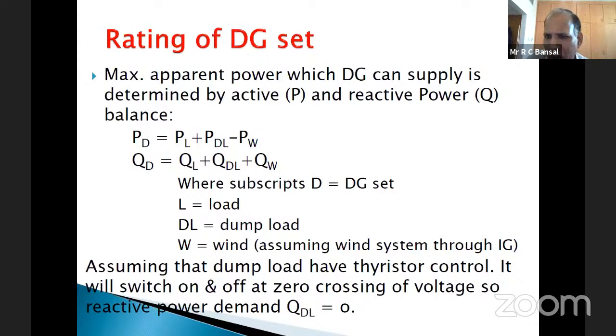If you have a hybrid power system with wind and diesel, and excess power is being generated from the wind system, where will this excess power be utilized? It can just be dumped into the dump load, because we have to maintain a balance between real power generation and demand in the real-time system to maintain frequency.